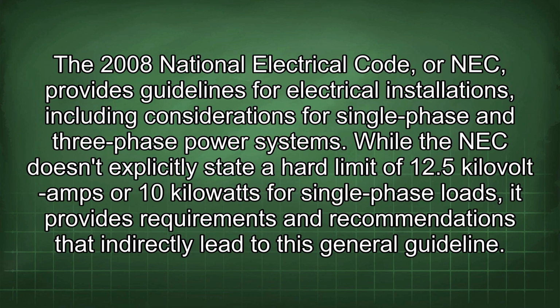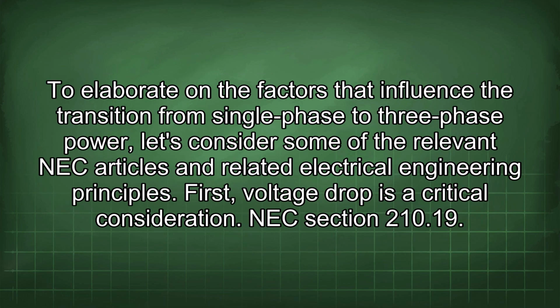The 2008 National Electrical Code, or NEC, provides guidelines for electrical installations, including considerations for single-phase and three-phase power systems. While the NEC doesn't explicitly state a hard limit of 12.5 kilovolt-amps or 10 kilowatts for single-phase loads, it provides requirements and recommendations that indirectly lead to this general guideline. To elaborate on the factors that influence the transition from single-phase to three-phase power, let's consider some of the relevant NEC articles and related electrical engineering principles.